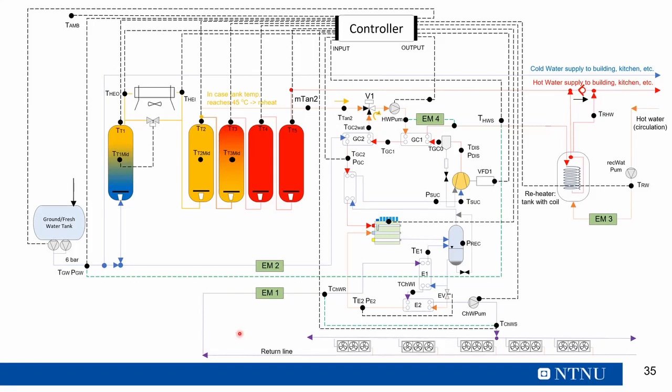So this looks a bit complex, but bear with me. Let me try to explain this system. We are going to design two gas coolers after the compressor, as you may need different temperature levels of water which are required in the hotel. So by keeping that in mind, we are going to design two separate gas coolers for the unit.